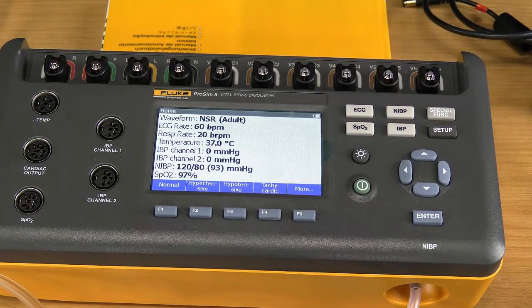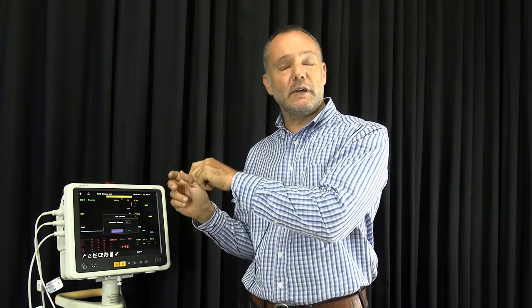Now, one thing I just need to say is when it comes to the way of testing NIBP, it's going to differ from brand to brand. Because in some brands like Philips, I have to apply the pressure to the monitor for calibration. In other brands, if I'm correct, I think the GE products, the patient monitor supplies the pressure to the simulator. So not every monitor works in the same way. Okay, so the method we're going to use is we're going to supply the pressure to the patient monitor.